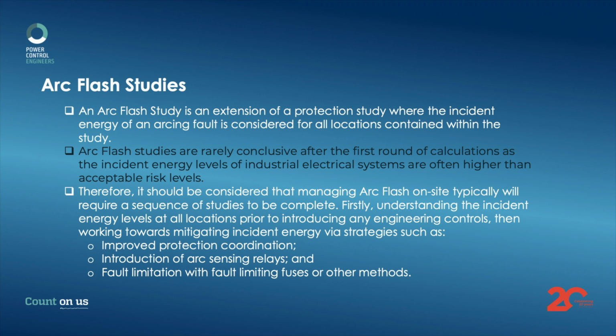Therefore, it should be considered that when managing arc flash on site, it will typically require a sequence of studies to be complete. Firstly, understanding the incident energy levels at all locations prior to introducing any engineering controls, then working towards mitigating incident energy via strategies such as improving protection coordination, introduction of arc sensing relays, and fault limitation with fault limiting fuses or similar.